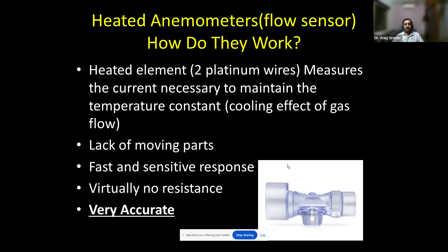But when the gas flows, these wires cool down, and because of the cooling, there is another extra current that is necessary to maintain that temperature. So based on the calculation of the current, we can calculate the flow, and from the flow, we can calculate the volume of the gas. Okay, it's very fast, very sensitive, very accurate, and very widely used these days. I mean, 20, 30 years ago, we were not using any of the flow sensors, but these days, in modern ventilation, you ought to use the flow sensors.